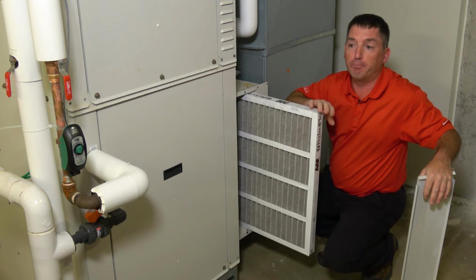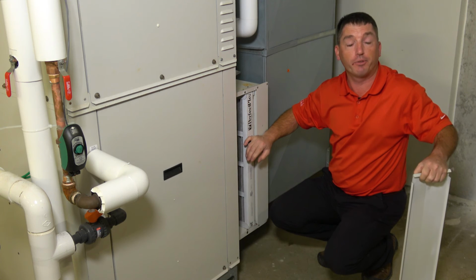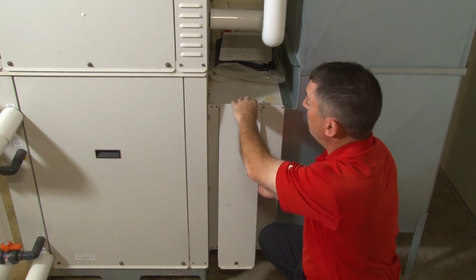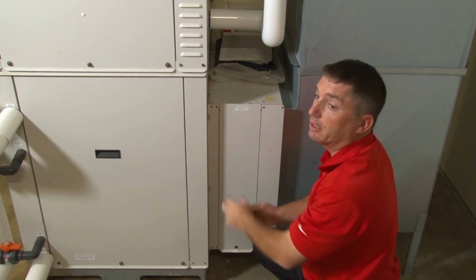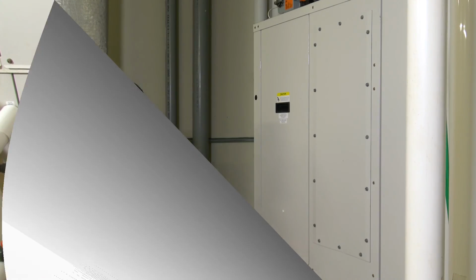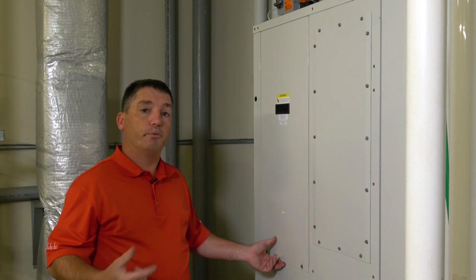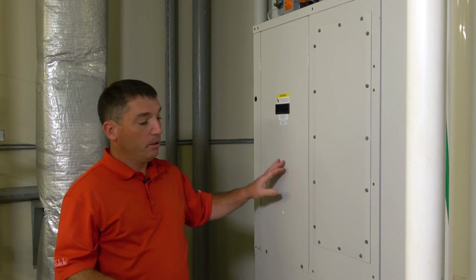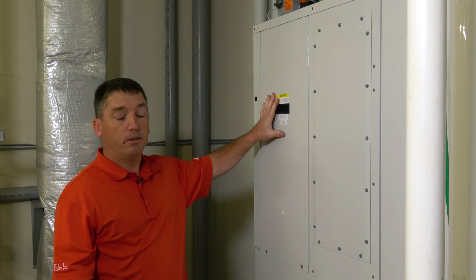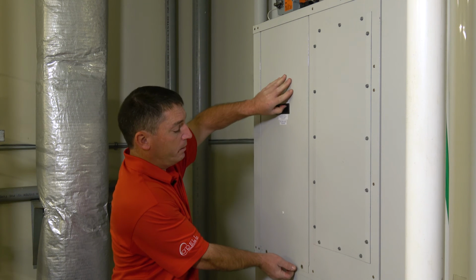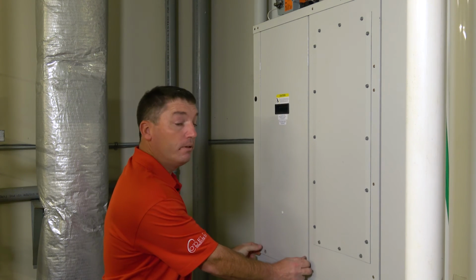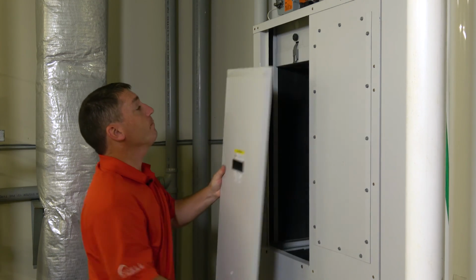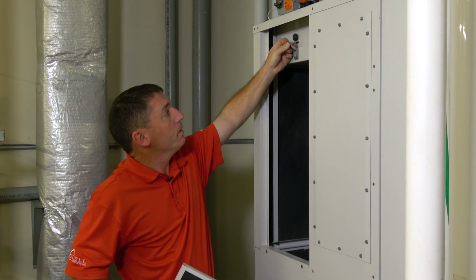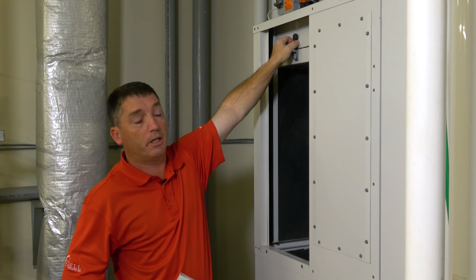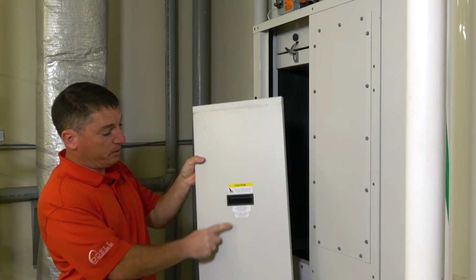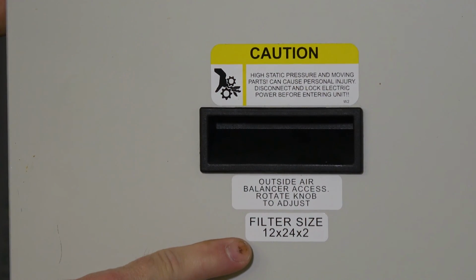Again, the blower on the unit runs 24/7, 365. So I would recommend changing the filters at least every 3 months. This unit also has the ability, during occupied periods, to bring in a small amount of outside air for ventilation. So on the left-hand side of the machine, we have another access door where we can access the filter for the outside air. And again, it's just a 2-inch pleated filter. The size is on the outside of the door.